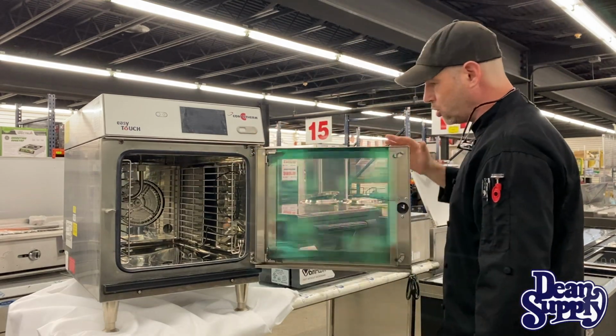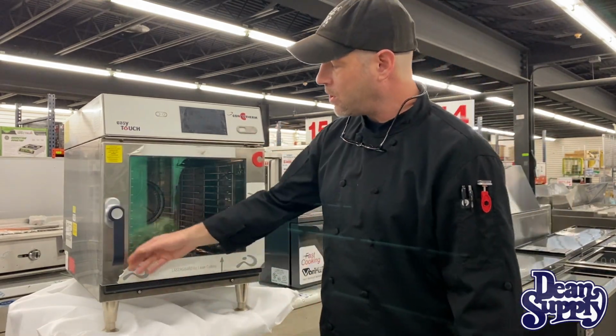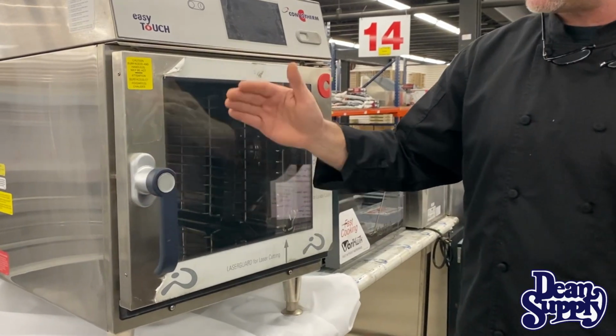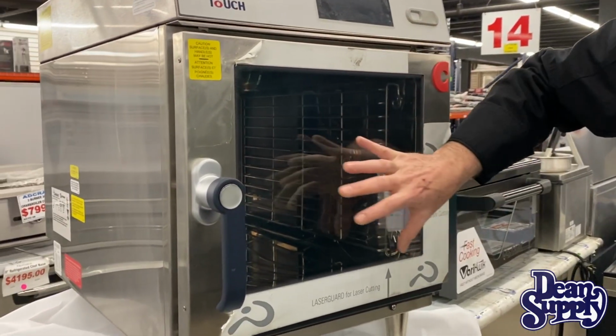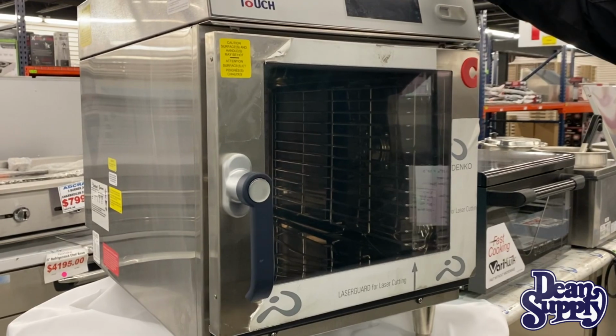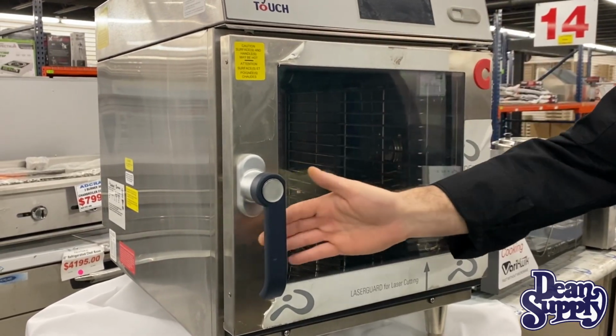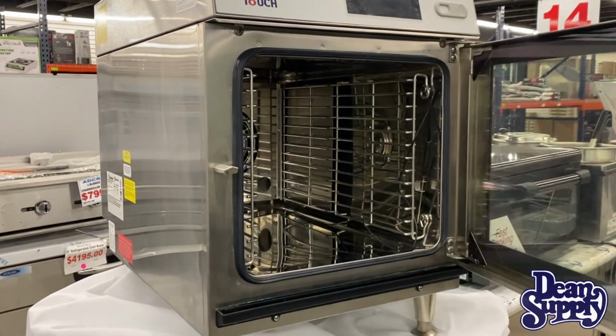It's got a slammable door, and it also has a 2-stage handle. When you open the door once, it cracks the door. If there's any condensation inside, it comes up through the top so it doesn't blow into the operator's face. And you do it again, and it opens up.